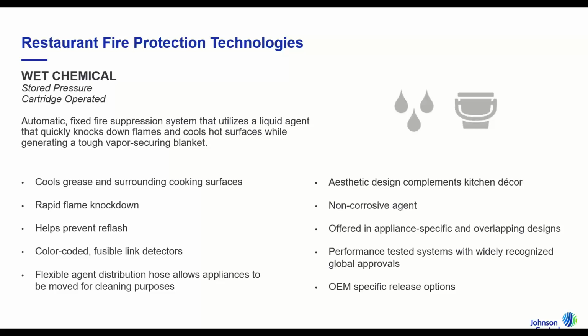Our suppression systems are aesthetically pleasing for the kitchen decor. So we do offer stainless steel enclosures so that it blends into the restaurant and it's not sticking out like the pull station you would want to. The agent is a non-corrosive agent, and we do offer in two different designs, which I'll touch on coming up here. All of the fire suppression systems are performance-based, and they meet UL 300 approval, which is a performance-based testing. It's widely recognized, and then we'll touch a little bit later on some regional and global approvals as well. I explained the stainless steel aesthetics that we have for stainless environments like a kitchen. We also have an OEM version, which would mount in an end cabinet of hoods such as Accurex.